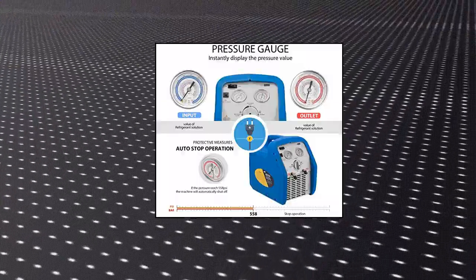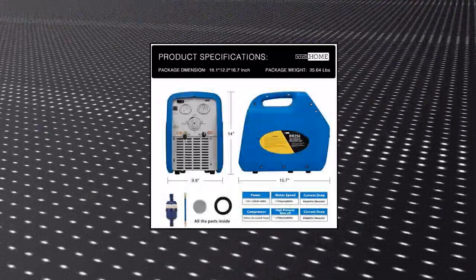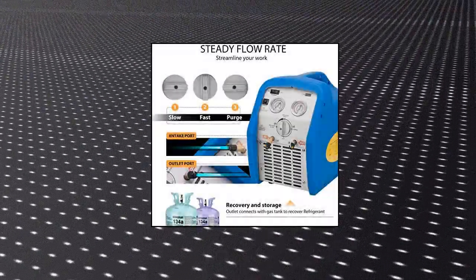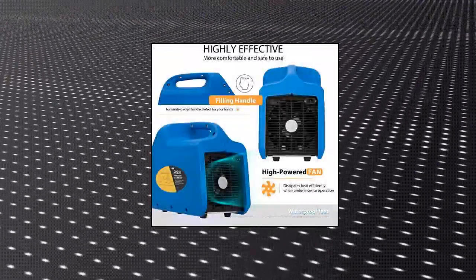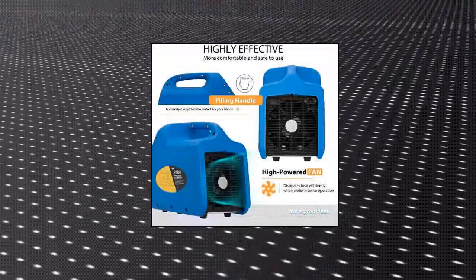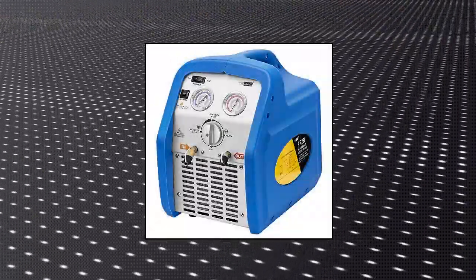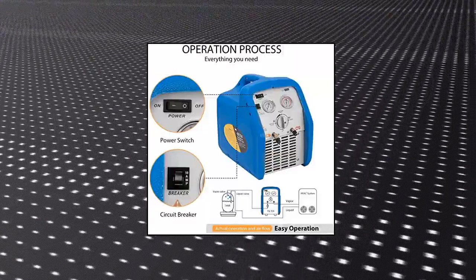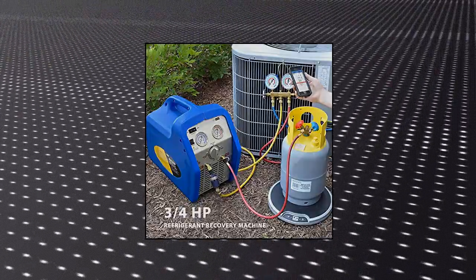VIVOHOME Single Cylinder Portable Refrigerant Recovery Machine. Compact design makes this refrigerant recovery machine easy to transport, while the design has its own eye-catching appearance, durable and reliable. This compressor has a maximum recovery speed of three-quarters of a horsepower that quickly recovers vapor and liquid refrigerants. Equipped with a high-pressure shutoff switch — when the pressure inside the system is above 38.5 bar, the compressor will automatically shut off to ensure safe operation.